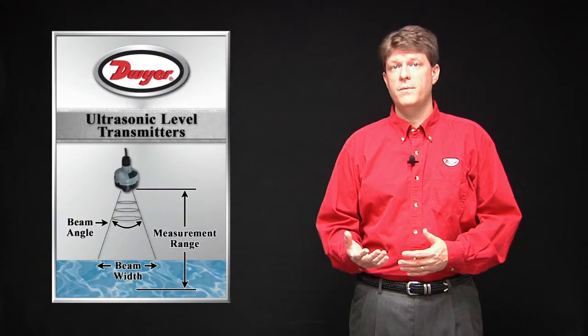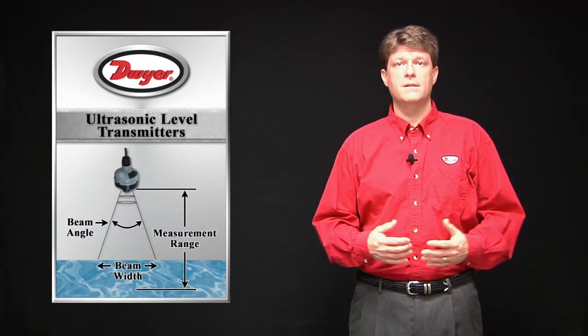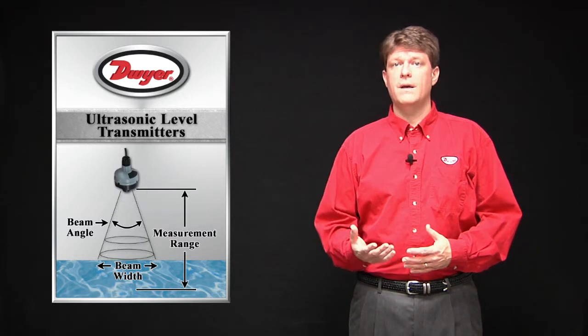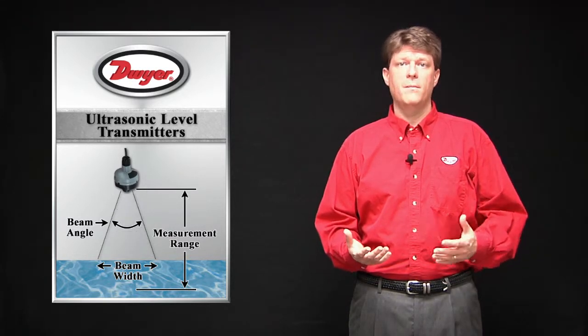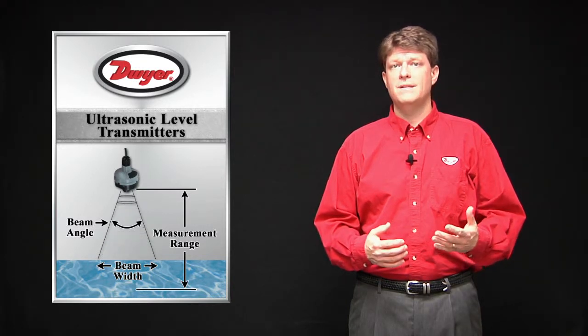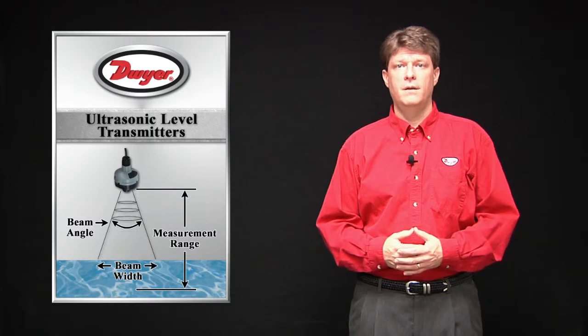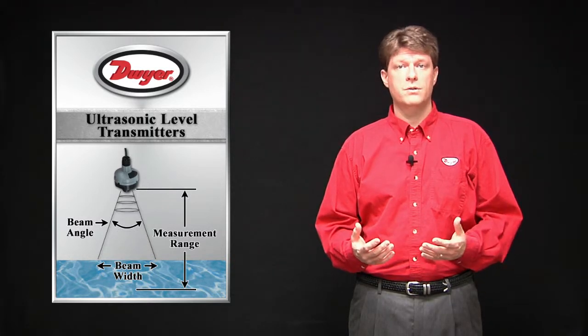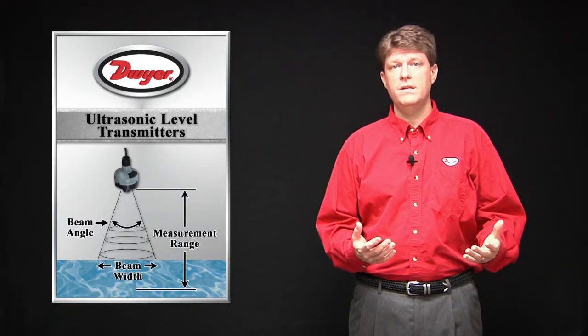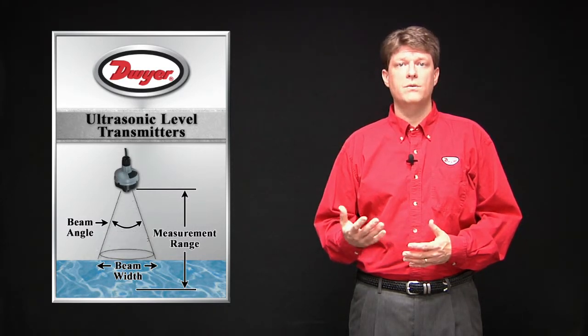The ultrasonic pulse from the transducer spreads out in a conical shape as it travels away from the sensor. This is referred to as the beam angle and is typically from 8 to 12 degrees. The beam width is the width of the sensing area that the sound pulse hits and reflects off of. If intrusions or obstructions are in the way of the pulse before it reaches the liquid surface, false echoes can be created, resulting in bad readings.